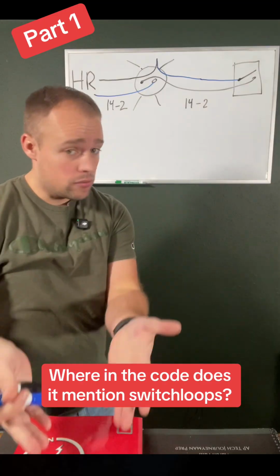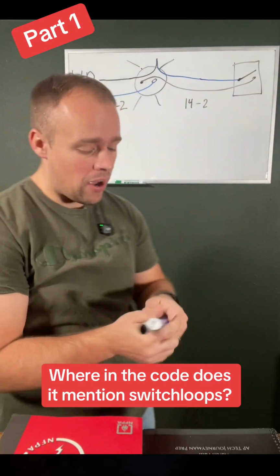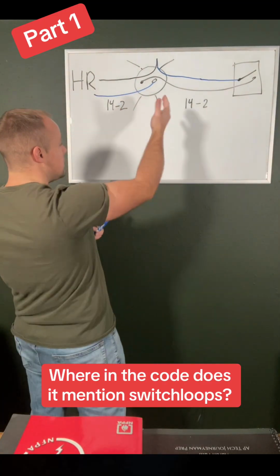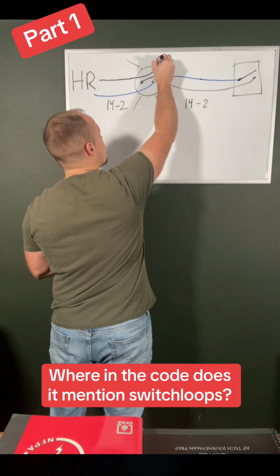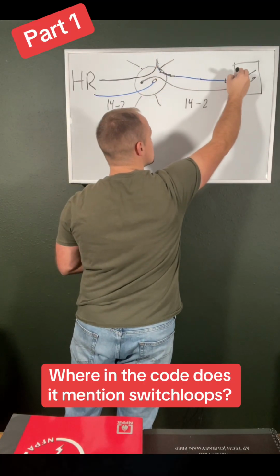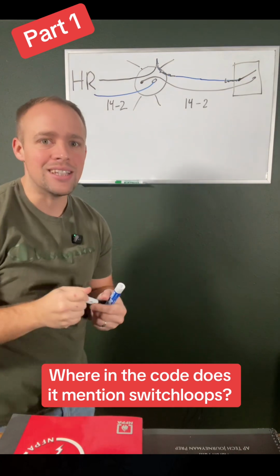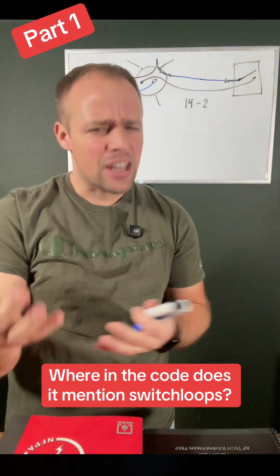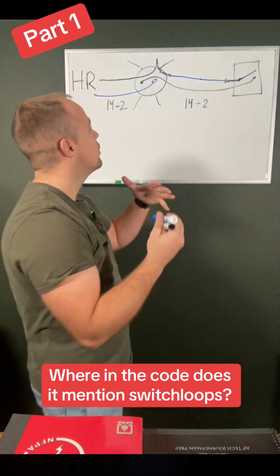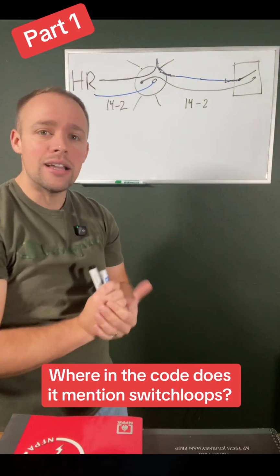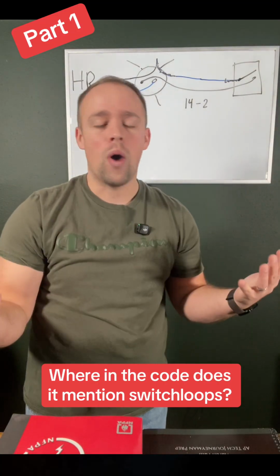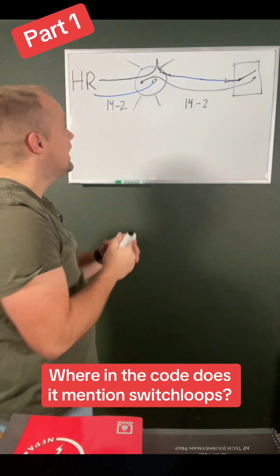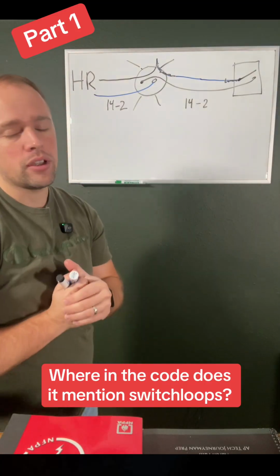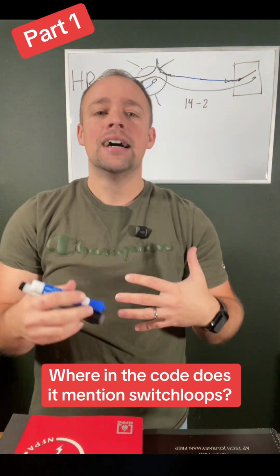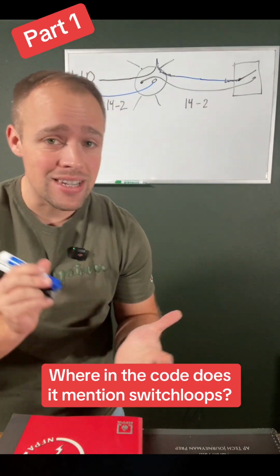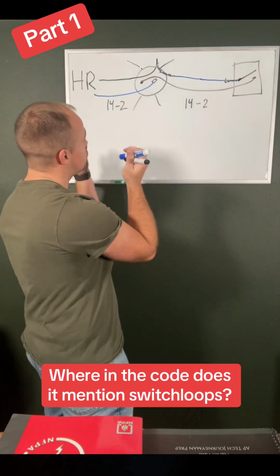Now, again, to code standards, comment down below if you found it, okay? We actually have to take this white conductor and label it black, okay? We don't want any future electricians to open up the switch box and see a white conductor and think, is that a neutral? We don't want them to think that. They have to understand that this is an ungrounded conductor, even though it is white by manufactured design. We have to tape it. You have to mark it with marker, whatever the case is, so that it's clear that it's an ungrounded conductor, not a neutral. So this is a switch loop.